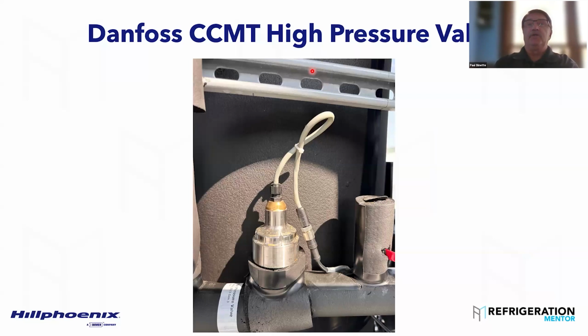If you feel you're having any issues with your HPV, I tell everybody every year when you do your maintenance, you change your filters, you change your separator, you change your suction dryers, you check and clean your inline strainers in the oil feed lines to calibrate that valve. You know, you calibrate that valve, you calibrate your transducers, you calibrate your temp sensors, because those are what keep your rack working efficiently.